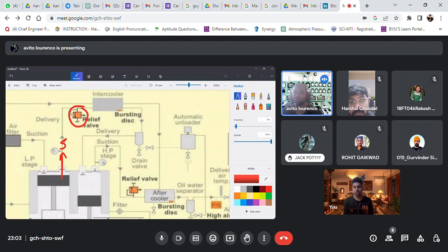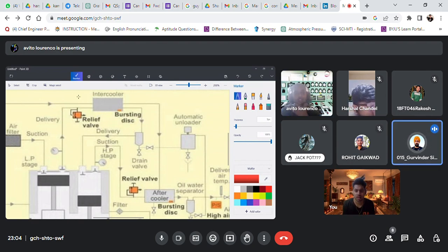So that means this will be set at 103%, 3% excess of 5 bar, so that if the pressure suddenly rises to 8 bar, this will make an alarm. But after it goes over here, if the water pressure, which is at 1 to 2 bar, and a leak takes place, then the bursting disk will be activated. But 103% of 5 bar is not 8 bar. No, I'm just saying whatever that value is. It is 3% of the rating, not more than 3%, so it is something like 5.6 bar. Absolute 103% will be the rating of whatever the pressure is, and it will be 3% excess, not more than 3%.